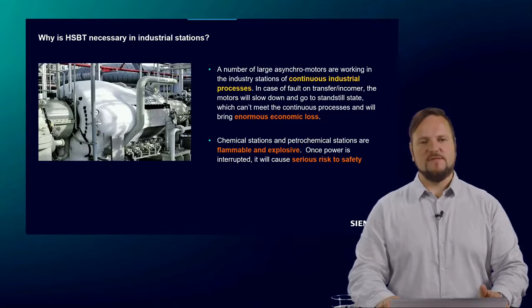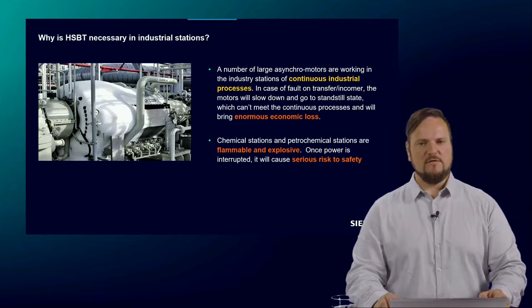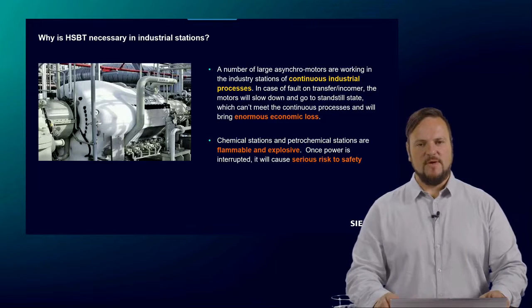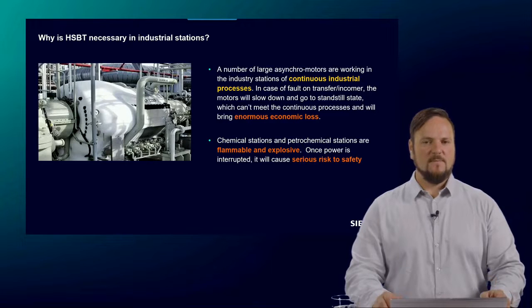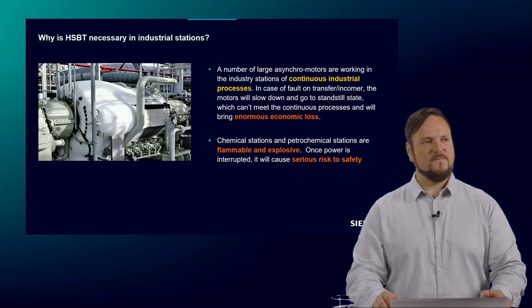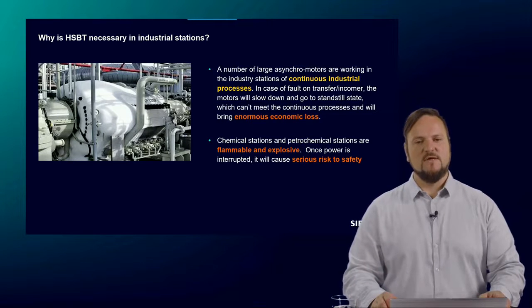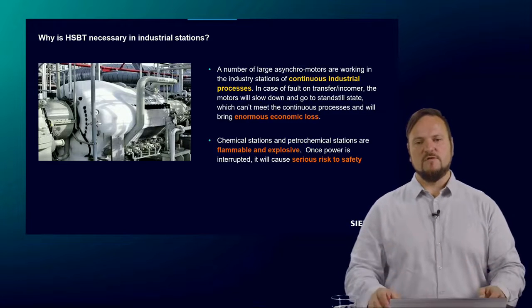Why is the HSBT necessary for industrial stations? In industrial stations, there are large numbers of asynchronous motors working continuously — for pumping, heating systems, and so on — requiring uninterrupted energy supply. In case of a fault in the incomer or transformer, motors on the motor bus will slow down and go to standstill, which means we can't meet continuous process requirements and face enormous economic losses. In petrochemical and chemical industries, there is also a serious risk of explosion of flammable environments — so not only economic loss, but also a serious safety risk.